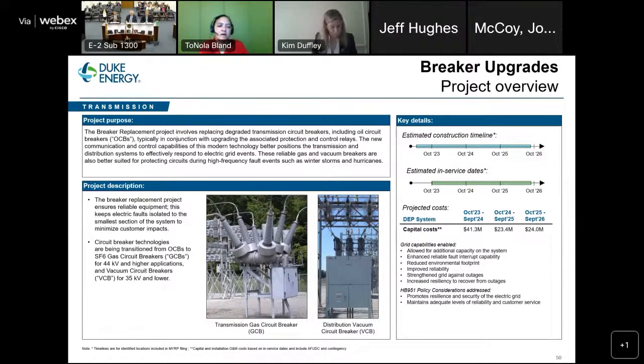So we're taking all these inputs, we're targeting the locations, and then we're replacing that oil circuit breaker with an upgraded technology. We're using vacuum circuit breakers. It's a vacuum chamber that extinguishes or prevents an arc from occurring for distribution level voltages. So that would be transmission assets in a transmission substation, less than 44 kV. And then for the higher voltage assets, we're using pressurized gas breakers, which is the state-of-the-art modern standard for fault interruption at the transmission level. And again, as we upgrade those assets, we're installing upgraded protection and control relays, digital relays that can get us that additional information for remote monitoring and control of the grid.